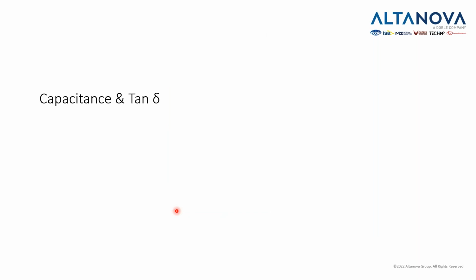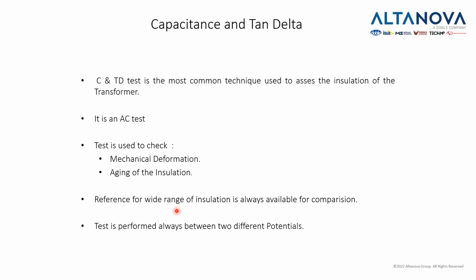Now, the next test will be capacitance and tan delta. Capacitance and tan delta is the most common technique used to assess the insulation of the transformer, and it's important to emphasize it is an AC test. With this, we can detect a change in the state of the insulation and possible mechanical deformation.